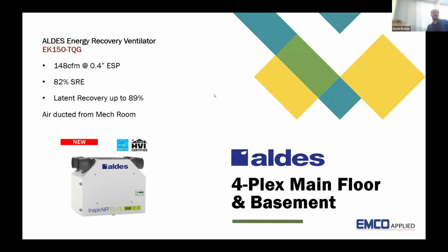For similar systems here, we've got the Aldes energy recovery units. They come with a variety of filtration options - standard is MERV 6, but MERV 8 and MERV 13 are also available. These units also have easily adjustable connections - the picture shows horizontal connections, but those connectors click off and you can change to a vertical connection straight away. These are also available with ECM motors instead of the standard 3-speed PSCs.